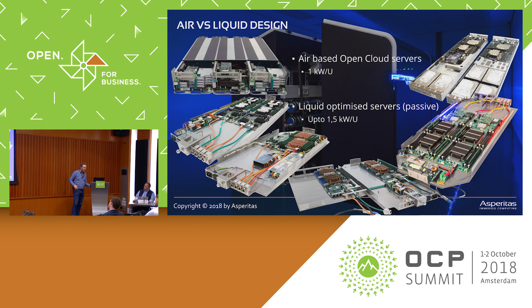This goes a bit further than just designing a chassis - it's about many different factors you currently take into account designing a server for air. For air, the chassis design is designed for stability and strength in a closed structure, packed so you can handle it horizontally. An immersion chassis, by contrast, is oriented vertically, designed for an open structure with reduced flow resistance for the higher viscosity medium you're using.